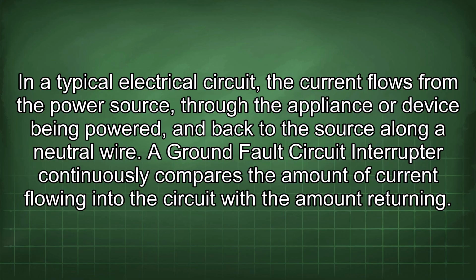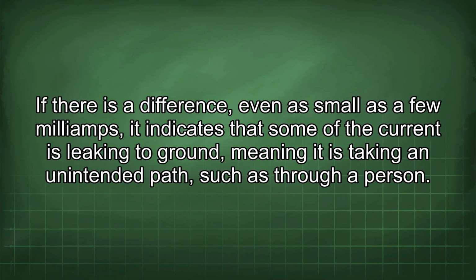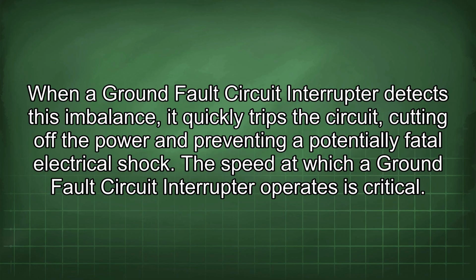A ground fault circuit interrupter continuously compares the amount of current flowing into the circuit with the amount returning. If there is a difference, even as small as a few milliamps, it indicates that some of the current is leaking to ground, meaning it is taking an unintended path, such as through a person. When a ground fault circuit interrupter detects this imbalance, it quickly trips the circuit, cutting off the power and preventing a potentially fatal electrical shock.